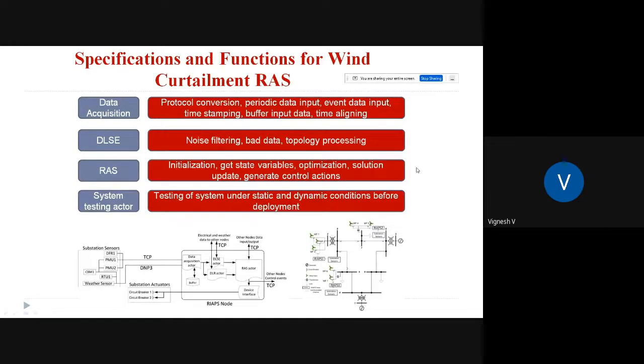The takeaway point is that distributed or decentralized control is more resilient to single point failures. Even though system performance might be deteriorated due to a single node failure, the entire system does not collapse, it's still up and running. That is one of the important advantages of decentralizing things, which we demonstrated using a use case like the wind curtailment remedial action scheme. Okay, I'll stop my presentation here. If you have any questions, I'll take them.